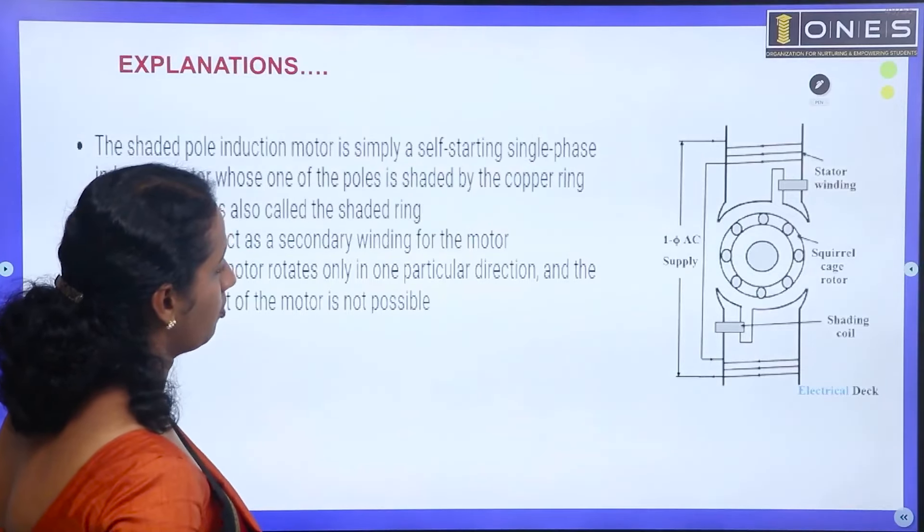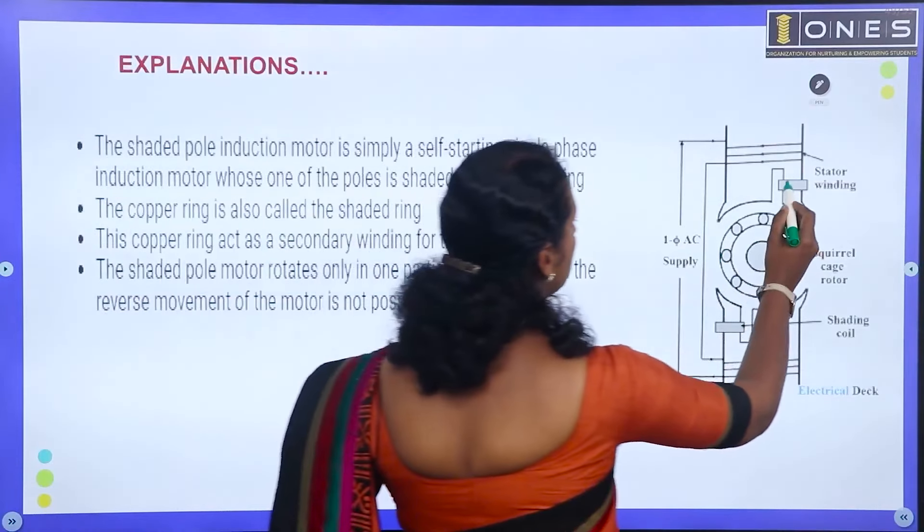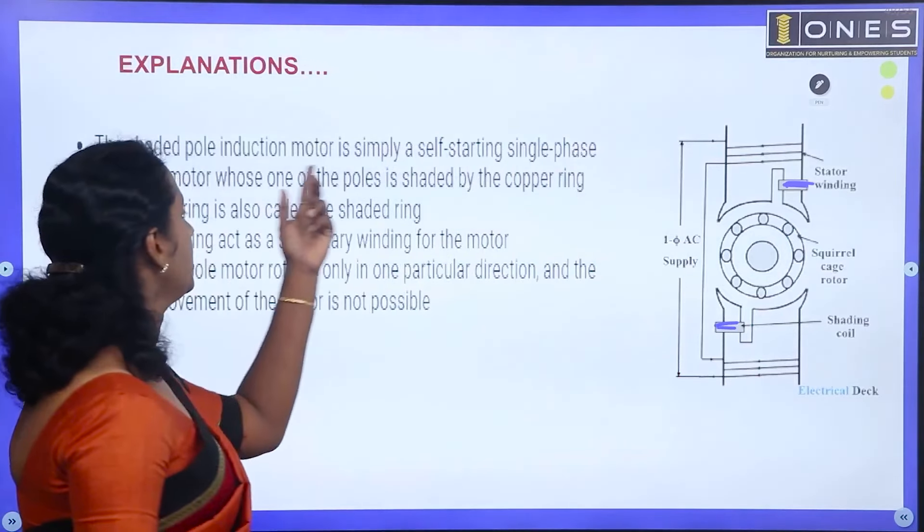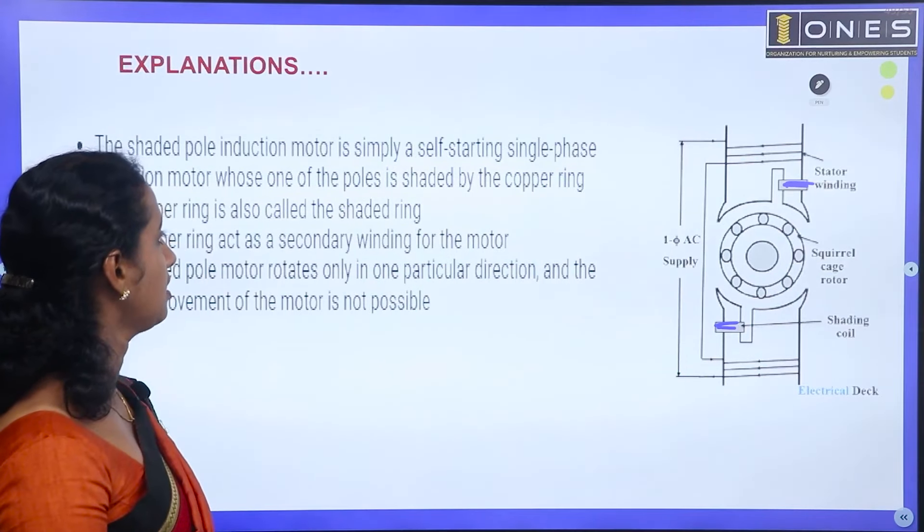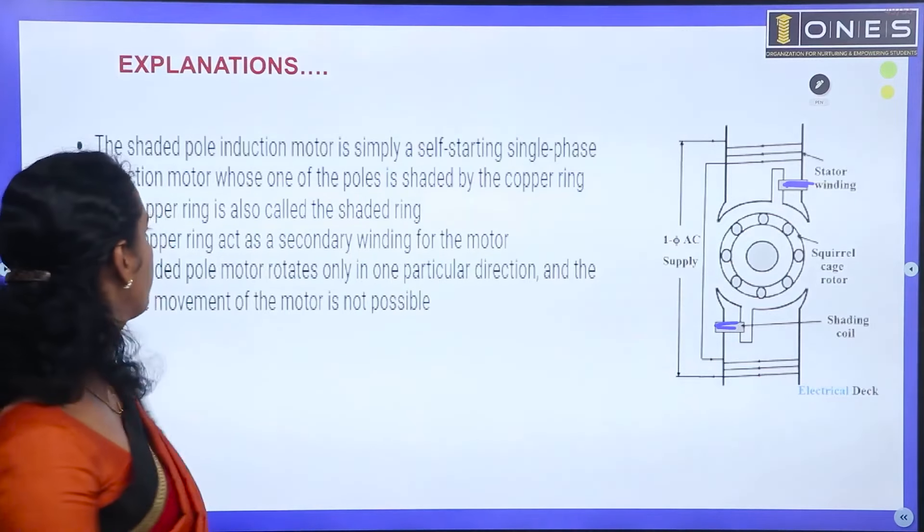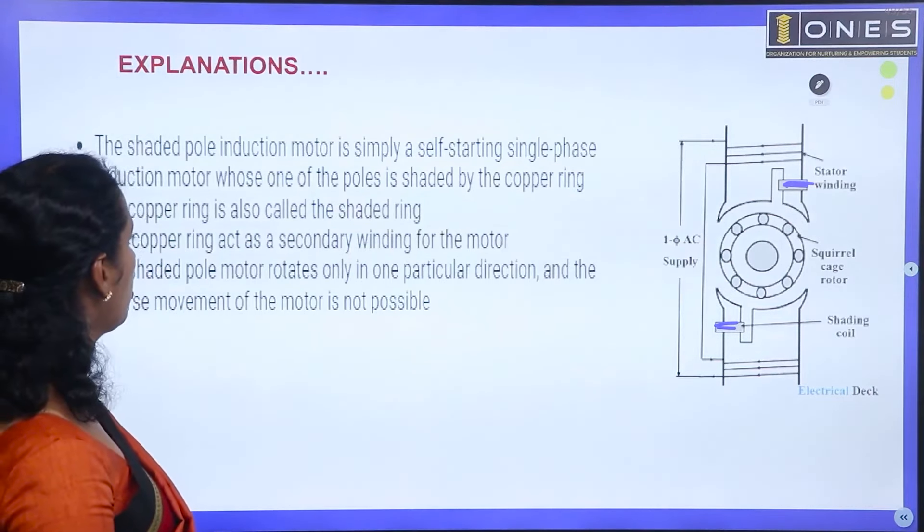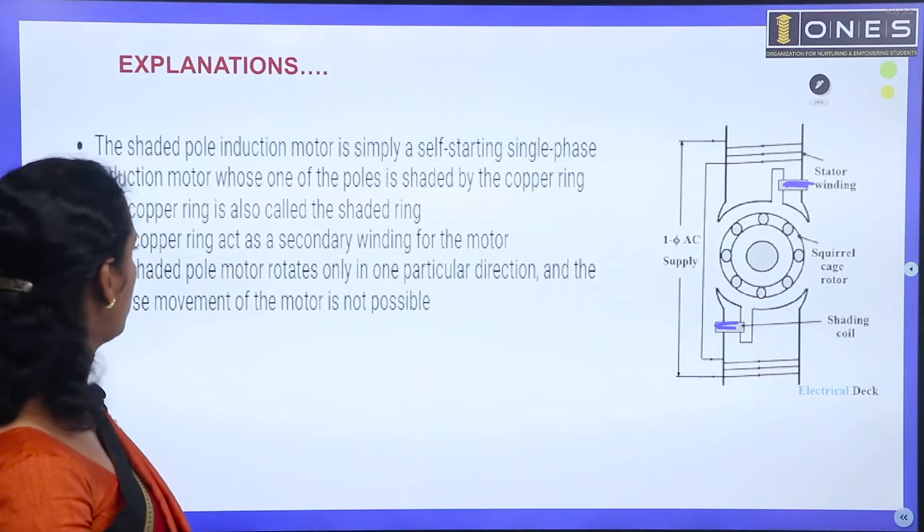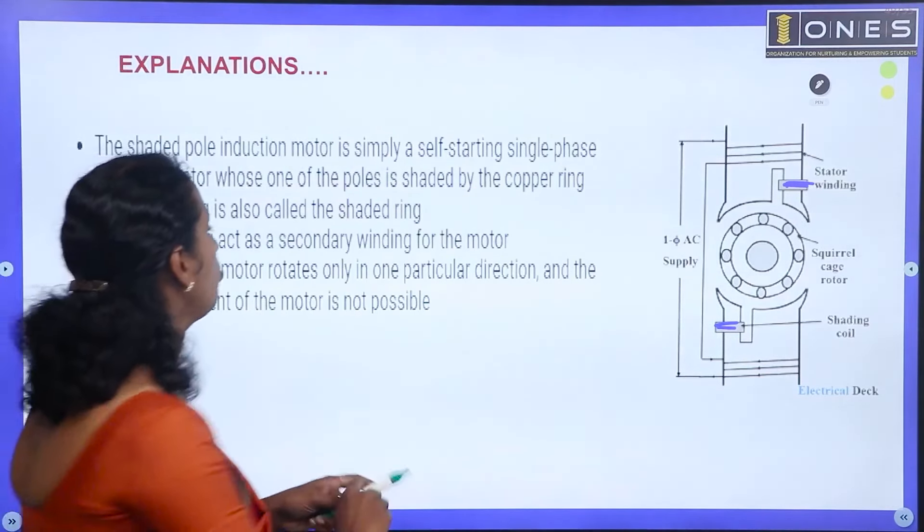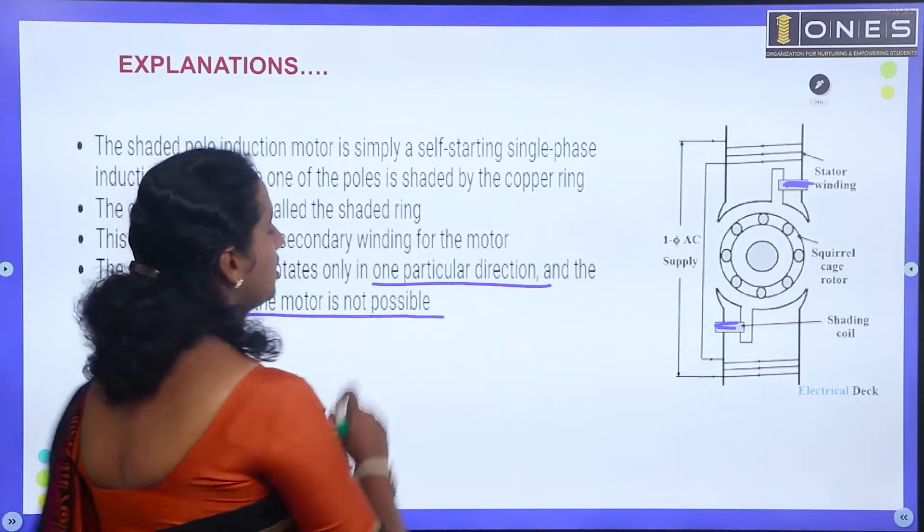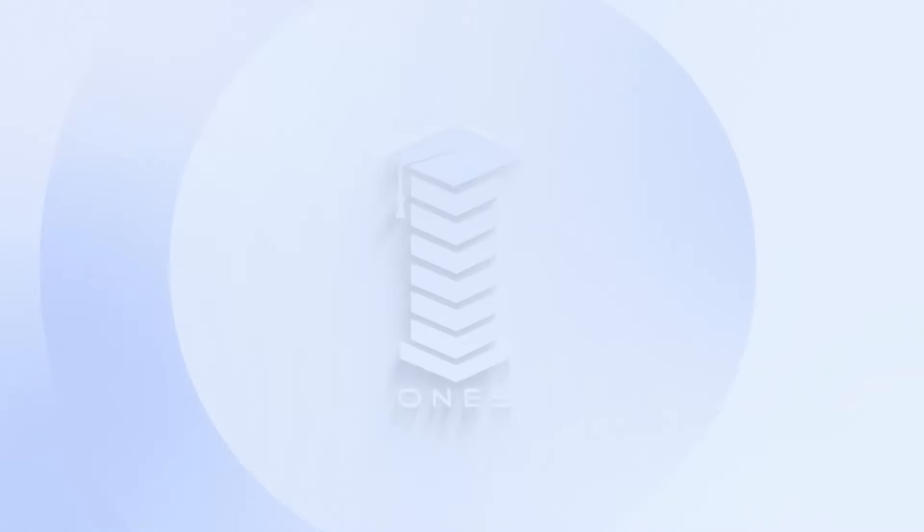And look at this. This is a shaded pole motor. You can see a band here, a copper band. The shaded pole induction motor is simply a self-starting single phase induction motor whose one of the poles is shaded by a copper ring. The copper ring is also called the shade ring. The copper ring acts as the secondary winding of the motor. The shaded pole motor rotates only in one particular direction, and the reverse movement of the motor is not possible.